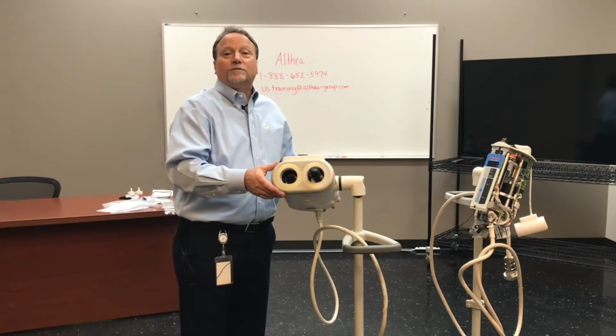Then you get an injector like this one, and hopefully you can see it on the screen. You see this yellow? That's contrast, up inside the plate seal. This has to be taken off and cleaned, which you'd normally do on a PM anyway, but that's how dirty this is. It's been there so long it's turned yellow.